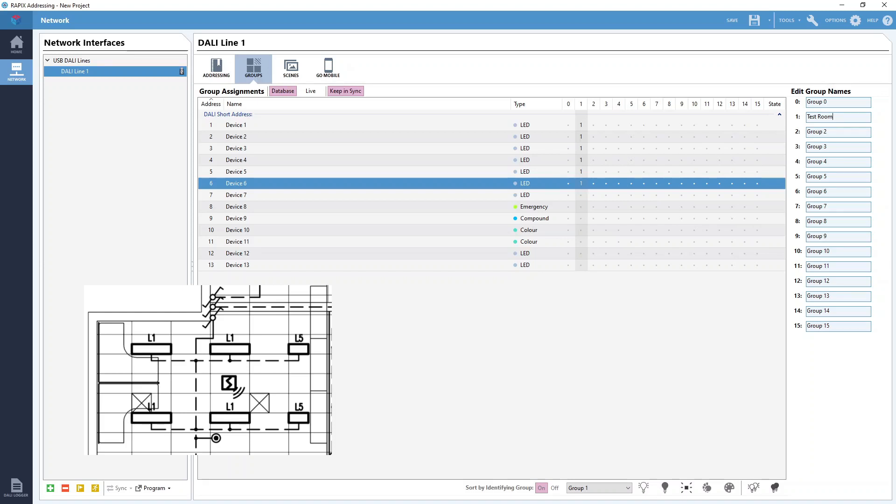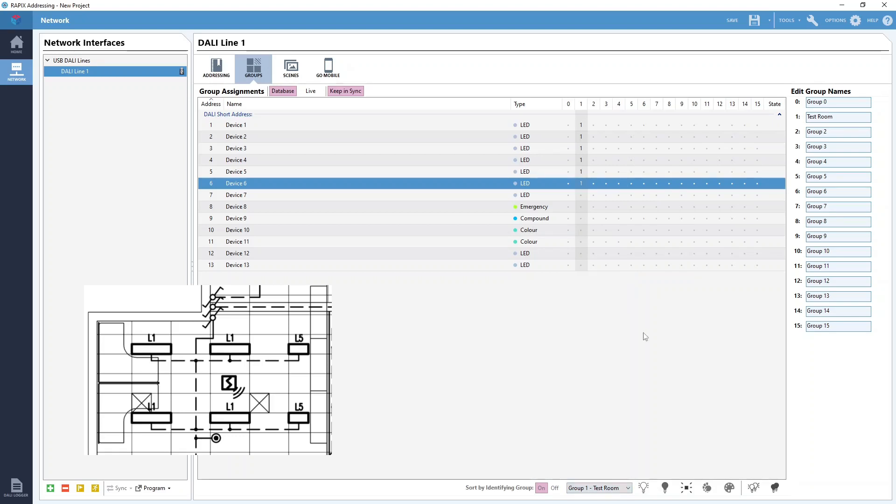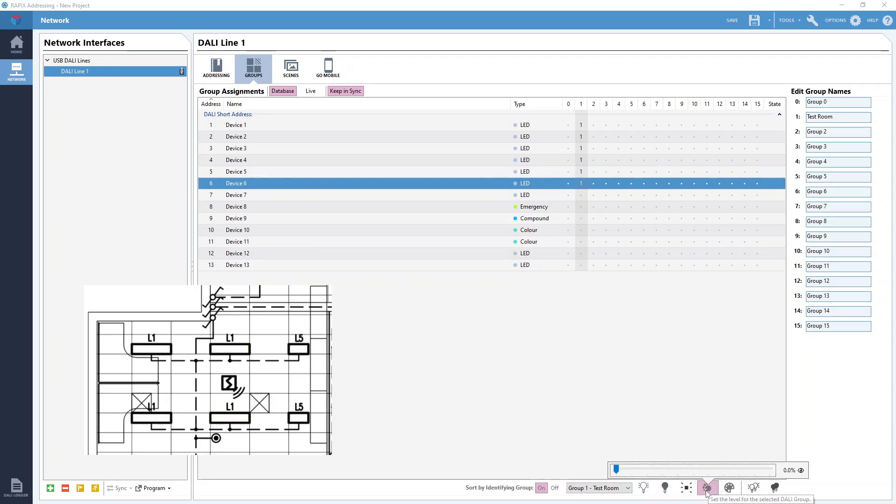Next if we want to test that we have programmed the group correctly we can go to the bottom bar here to this dropbox and select the group we want to test. When you name your group like we just did it will already have pre-selected it for you. Now these individual control buttons here will control the group we have selected rather than the selected DALI device. We can turn them on or off, flash them with the identify button, or dim them up and down with the slider.